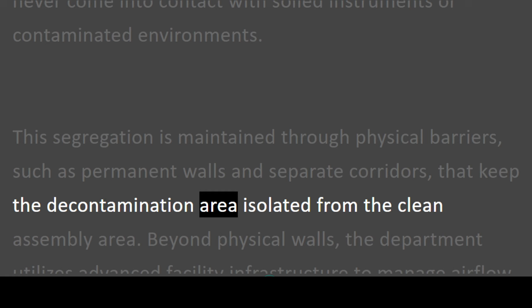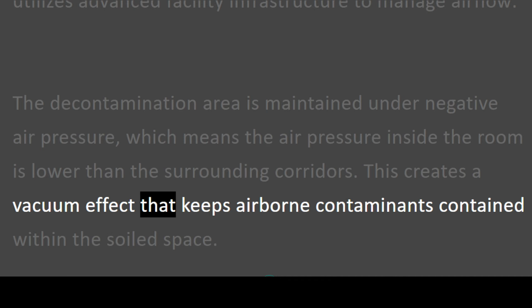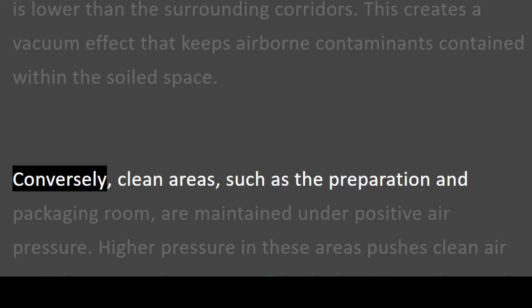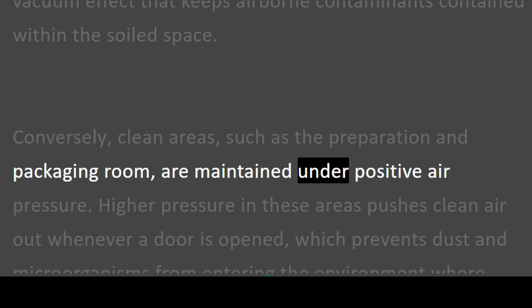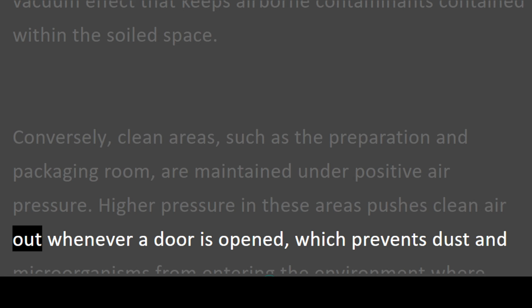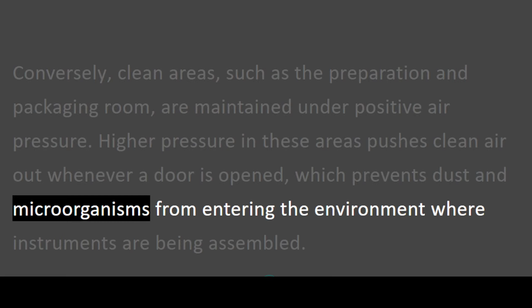Beyond physical walls, the department utilizes advanced facility infrastructure to manage airflow. The decontamination area is maintained under negative air pressure, which means the air pressure inside the room is lower than the surrounding corridors. This creates a vacuum effect that keeps airborne contaminants contained within the soiled space. Conversely, clean areas, such as the preparation and packaging room, are maintained under positive air pressure. Higher pressure in these areas pushes clean air out whenever a door is opened, which prevents dust and microorganisms from entering the environment where instruments are being assembled.